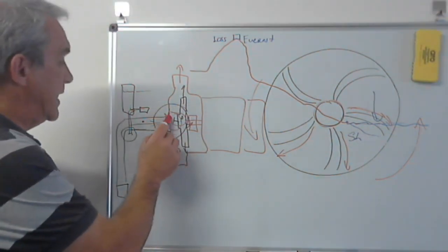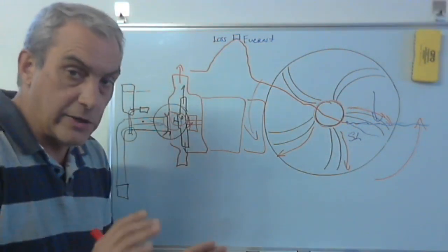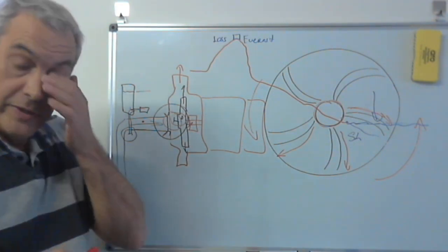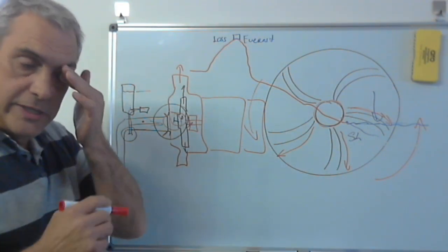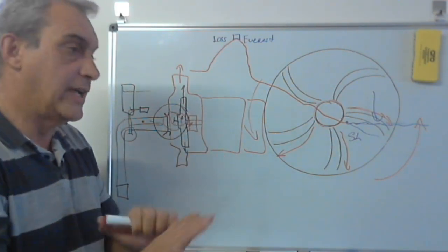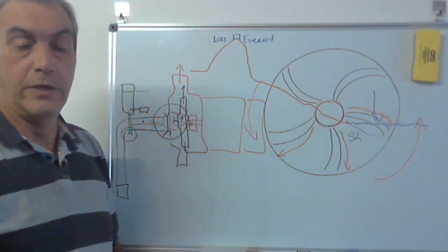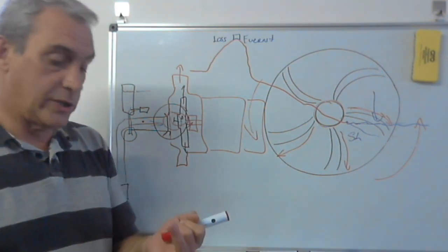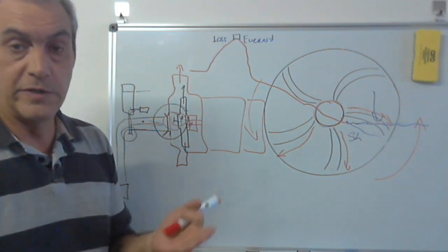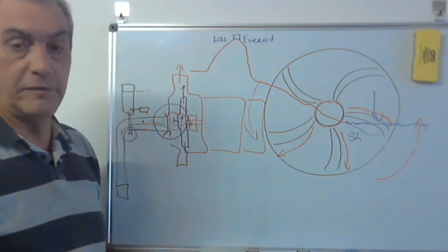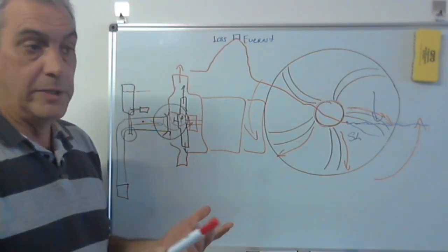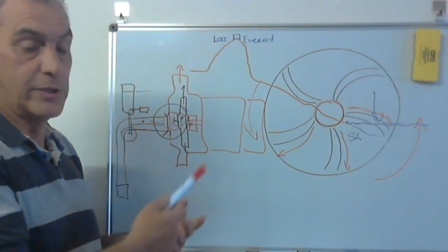And as long as everything is intact, no leaks whatsoever, not even the smallest leak, it must be completely intact. So if you want to assess why a pump's not working on a site, first thing you're going to look at is the suction. I guarantee you, you'll probably find a problem there. Unless of course the impeller's come apart, the motor's shot, it's not working, the pump is running in the wrong direction if it's three-phase, or power utility might have swapped phases on three-phase, now the pump's running backwards. It'll still pump at about a third of the pressure that it normally would.